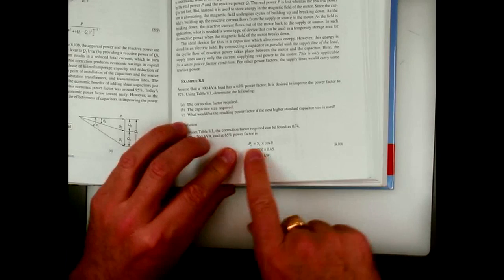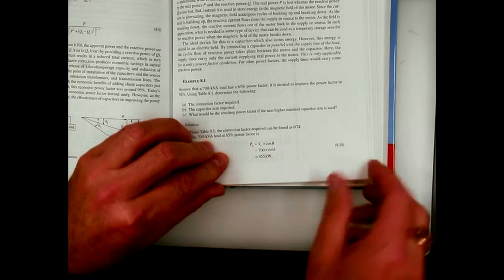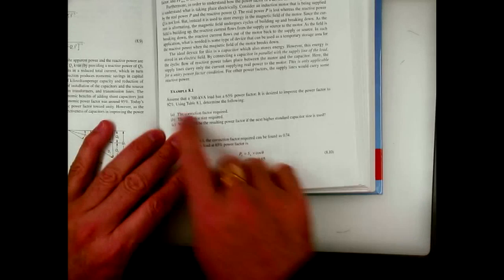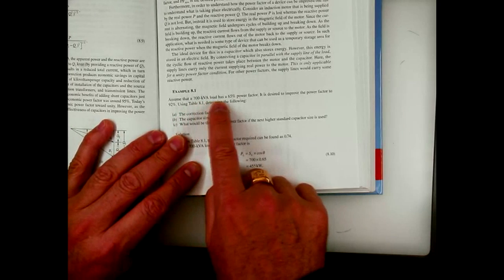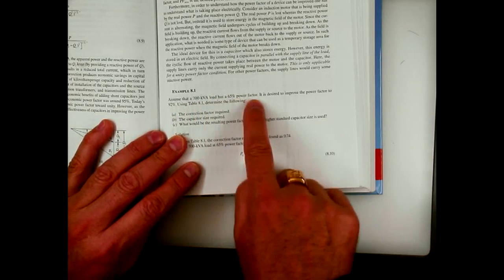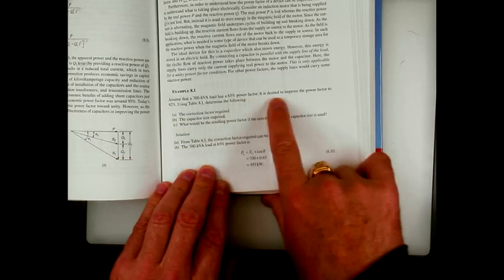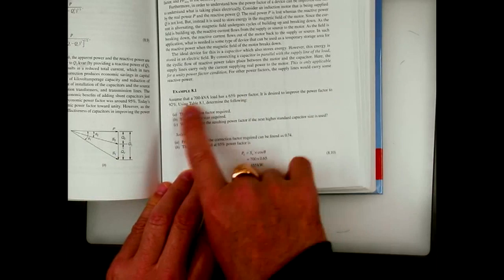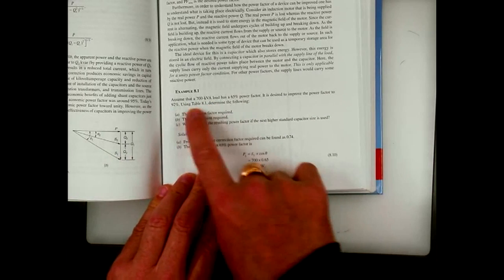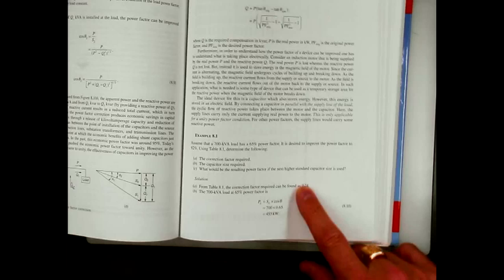So if you look at here, this equation, you've seen it before, right? In this case, what is this? Assume a 700 kVA load has a 65% power factor. Now you see why I'm using percentages in this chapter, because the book uses percentages -- not 0.65, but 65. It's desired to improve the power factor to 92%.